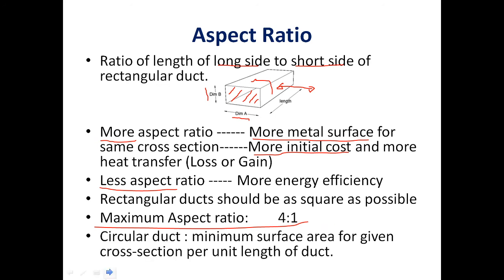The most ideal shape for a duct is circular, because it provides the minimum surface area for a given cross-sectional area per unit length. However, circular ducts are difficult to fabricate and install, so they are not commonly preferred. In practice, we use rectangular ducts with the minimum possible aspect ratio.